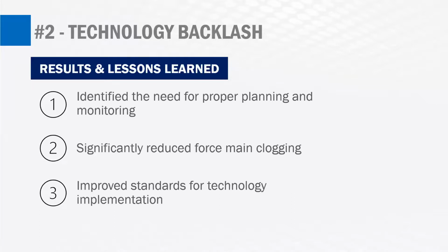The force main clogging was significantly reduced once the controls logic was worked out. The frequency of force main clogging virtually disappeared once that was worked out. And one of the key lessons learned in this audit was that the standards for technologies really needed to be improved. The technologies and control side of pump stations are a lot of the time glossed over when it comes to standards that are developed for pump stations, especially local standards for smaller municipalities. A lot of that is left up to the design engineer and the operators and maintenance staff. They do not actually have a lot of say in what's going to go into these stations. So it's best if those standards are improved.